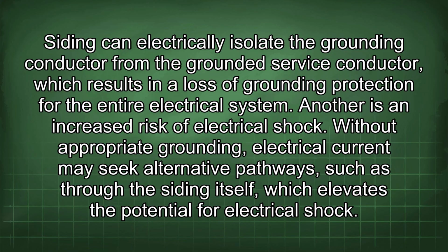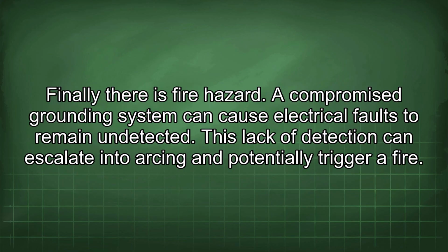Another is an increased risk of electrical shock. Without appropriate grounding, electrical current may seek alternative pathways, such as through the siding itself, which elevates the potential for electrical shock. Finally, there is fire hazard. A compromised grounding system can cause electrical faults to remain undetected. This lack of detection can escalate into arcing and potentially trigger a fire.